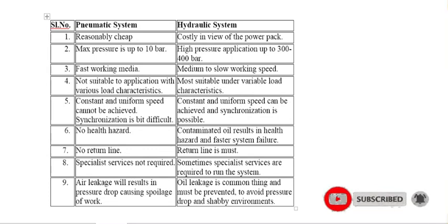In pneumatic system there is no health hazard, whereas in hydraulic, contaminated oil may result in a health hazard. No return line is required for pneumatic system, whereas hydraulic system must require a return line. I'll explain in the cylinder section what it is. Pneumatic system does not require any specialist service. A semi-skilled person can handle the pneumatic system, but hydraulic system requires a specialist service.